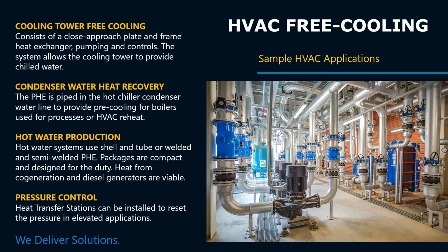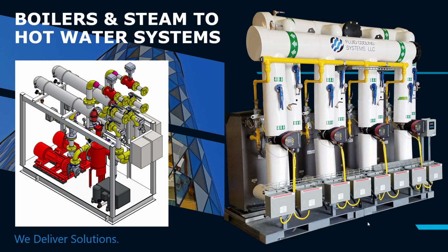Another use of heat exchangers is for pressure control. In high-rise buildings, heat transfer stations can be installed to reset the pressure in elevated applications. FCS can provide steam to hot water modules as depicted on the left, featuring shell and tube or semi-welded stainless steel plate exchangers, and of course duplex pumps and the controls for producing hot water. On the right we see a photograph of a 4-boiler system that includes the hydronic controls and the valves and the pumps.